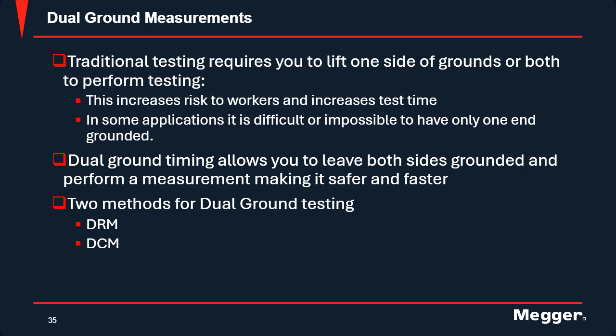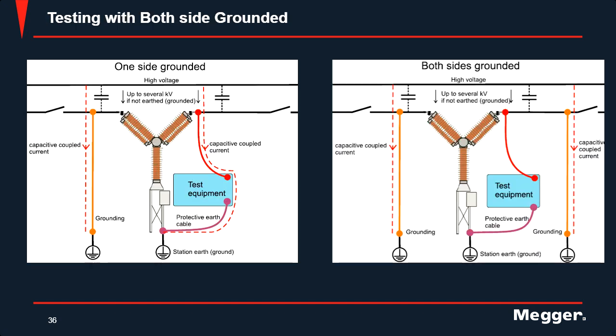You can do timing with DRM. However, it's going to be a resistive timing, and there's a lot of interpretation because you have to base it off the ground loop and the resistance of your contacts. So here's a little demonstration again. As you can see, on the left, with one side grounded, you do have that capacitive current going through your test set, which is a risk for fault or damage to your test set. And then when you have both on, you're in a nice, clean, safe zone to work in.